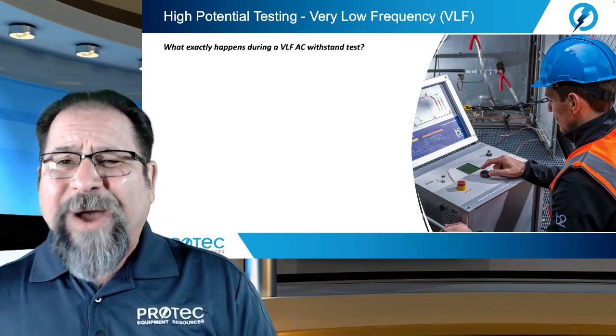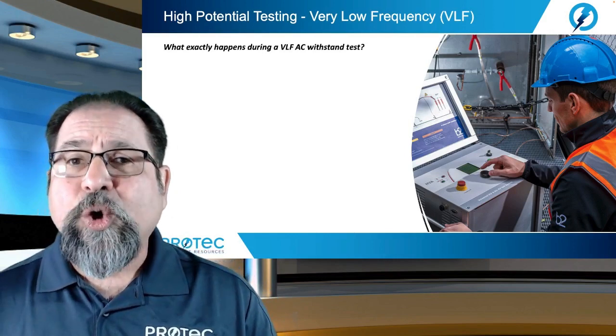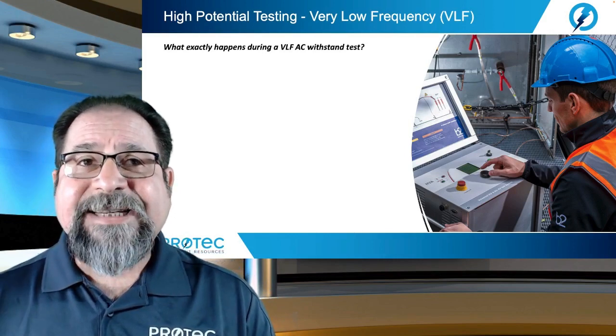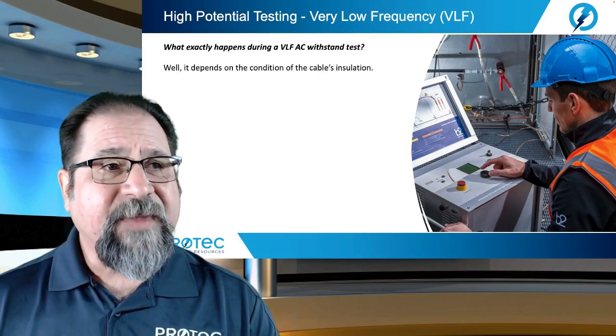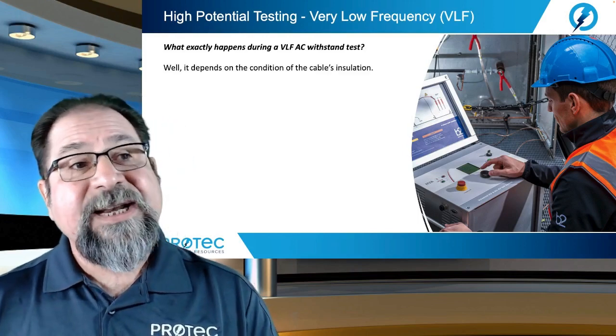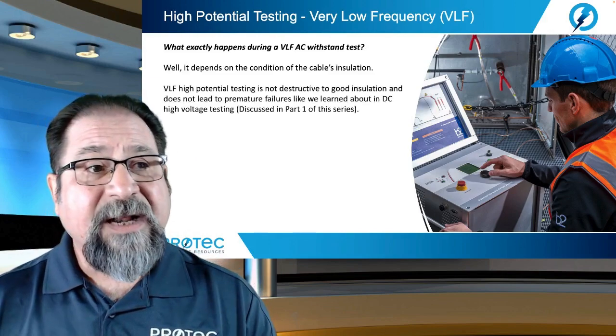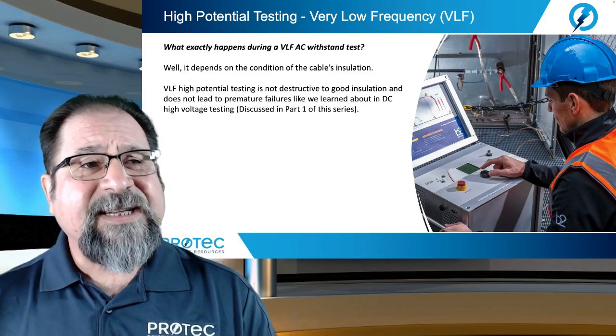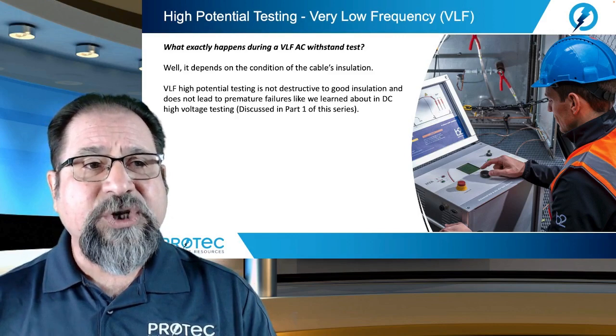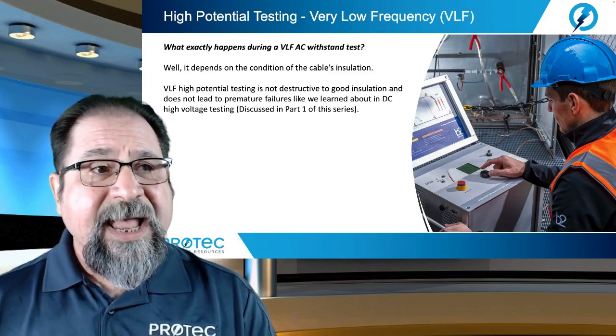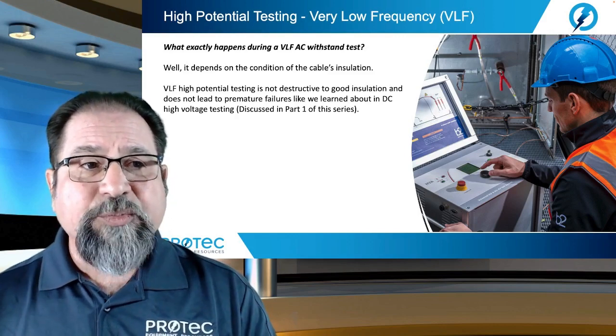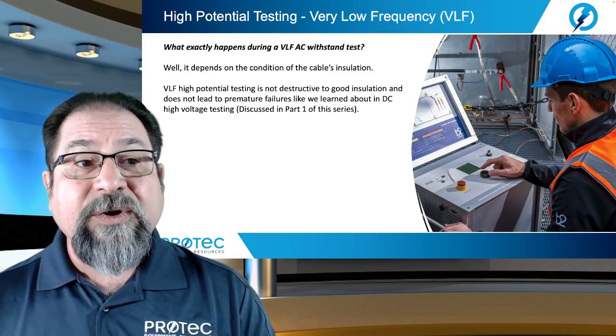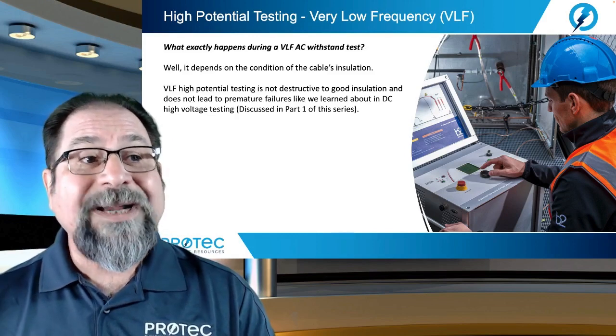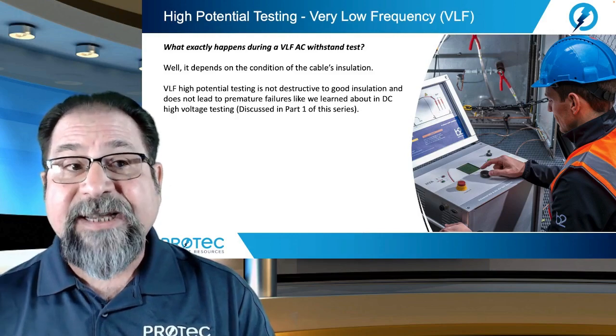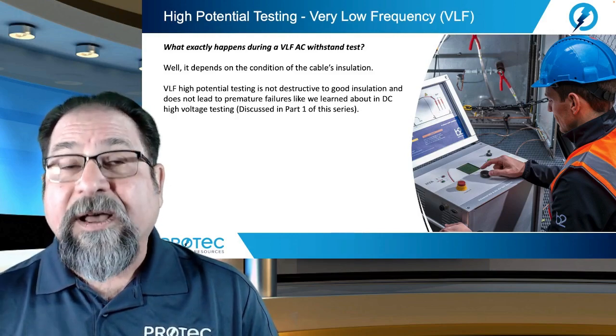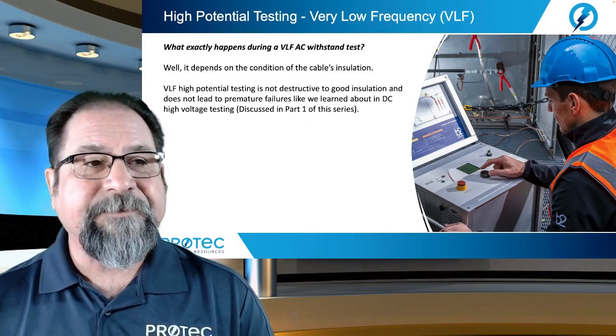Now, what exactly happens during a VLF AC withstand test? Well, it depends on the condition of the cable's insulation. VLF high potential testing is not destructive to good insulation and does not lead to premature failures like we learned about in direct current or DC high voltage testing that we discussed in part one of this cable testing series.